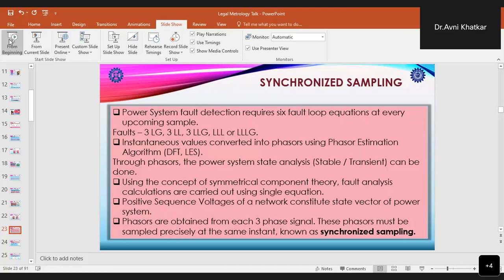And the positive sequence voltages of a network constitute the state vector of the power system. And hence the phasors which are obtained from each 3-phase signal must be sampled precisely at the same instant, and this precise sampling of the phases at the same instant is what is known as synchronized sampling. And by having this synchronized sampling, we get synchrophasors. Synchrophasors are nothing but the phasors which represent the fundamental of an AC signal, whose magnitude is the RMS value of the fundamental amplitude, and the angle is the difference between the signal fundamental angle and the phase angle of the cosine at the nominal signal frequency, which is synchronized to the UTC time.